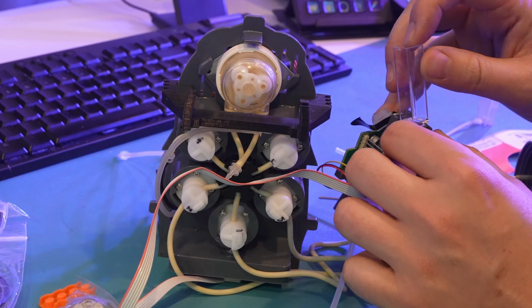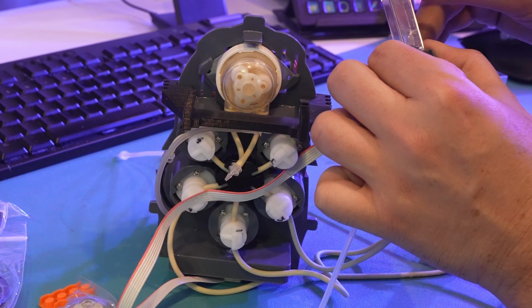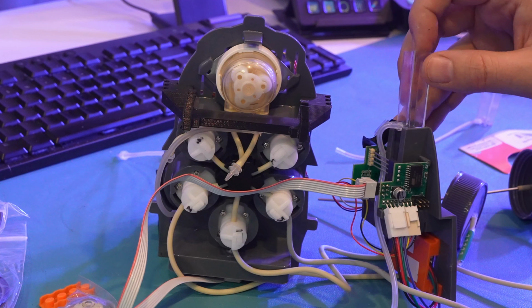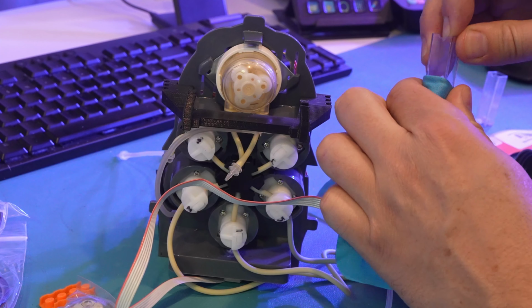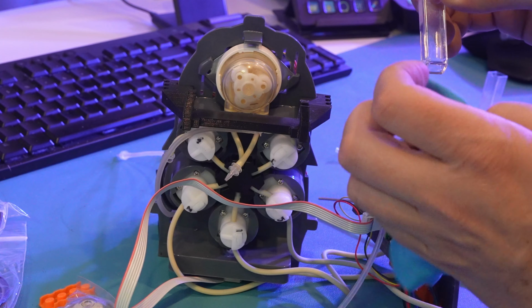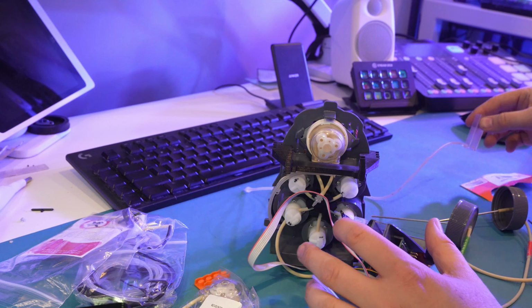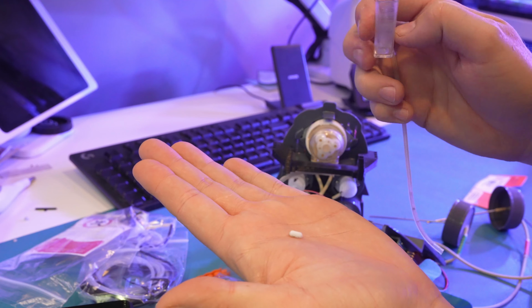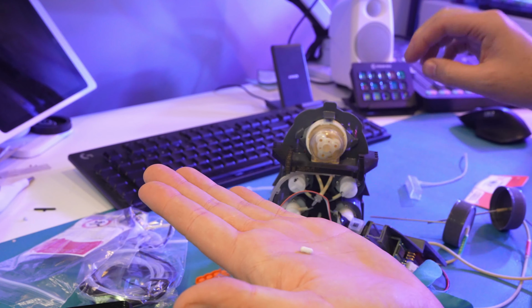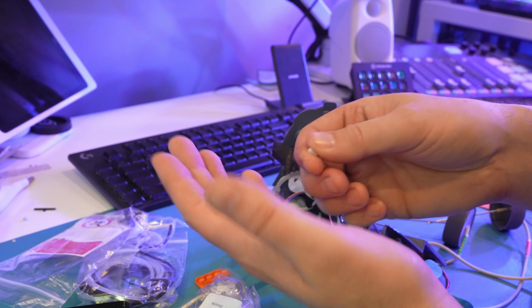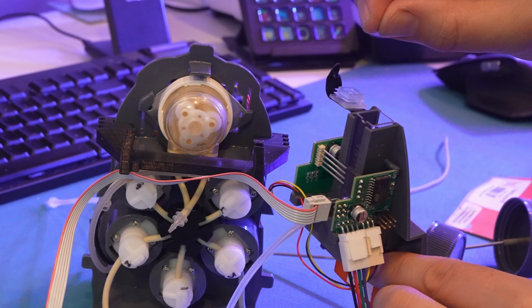Now, this does use a colorimeter, so try and make sure you don't get any fingerprints or smudges on it. I just saw that I got one, so I'm just going to use a little glass cloth just to make sure that's cleaned off nicely, and slide our cuvette back inside. Now the old cuvette does contain a little tiny pill, and this is our magnetic stir bar. So we're going to give this one a wipe off and reinstall it to the new cuvette. And once it's installed, we can put our little cap back on top.